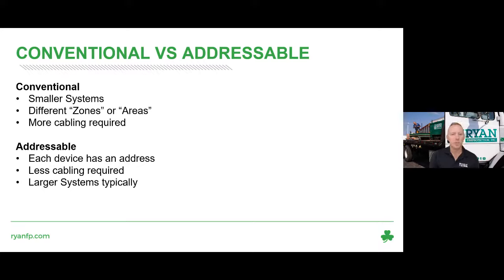Typically, these are larger and more complex systems, though they don't have to be. That's just what we see out there in the market. One key thing is addressable systems actually require less cabling and wiring, which is a fun fact, and they're much easier to diagnose problems with than a zone system. There are absolutely plenty of scenarios where a zone system or a conventional system makes perfect sense.